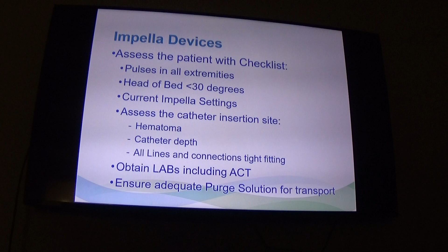The device actually has enough power for 60 minutes, so just make sure you're always plugging it in. And this goes for balloon pumps and any device. Always make sure it's plugged in to wall power as much as possible. You only want to use the batteries when you're transferring. And again, it also provides the purge solution, but most importantly, it provides recommended fixes. So you're not on your own. This device actually tells you what to do in most cases, and all you need to do is do it. So this is what it looks like.